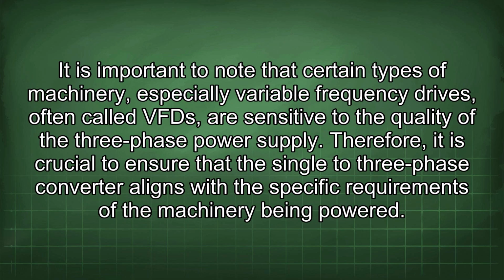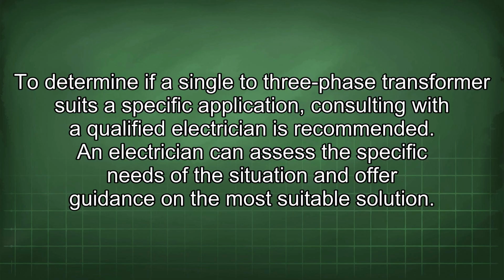It is important to note that certain types of machinery, especially variable frequency drives, often called VFD, are sensitive to the quality of the three-phase power supply. Therefore, it is crucial to ensure that the single to three-phase converter aligns with the specific requirements of the machinery being powered. To determine if a single to three-phase transformer suits a specific application, consulting with a qualified electrician is recommended. An electrician can assess the specific needs of the situation and offer guidance on the most suitable solution.